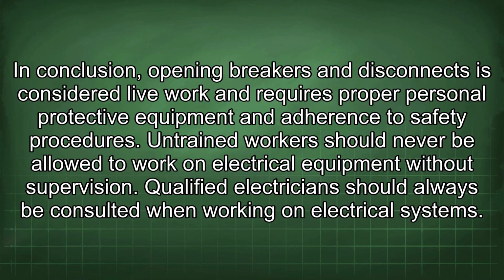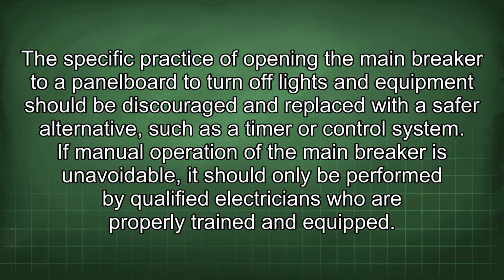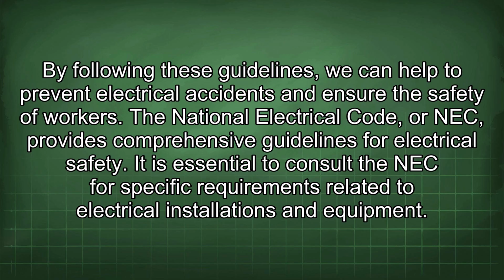Qualified electricians should always be consulted when working on electrical systems. The specific practice of opening the main breaker to a panel board to turn off lights and equipment should be discouraged and replaced with a safer alternative such as a timer or control system. If manual operation of the main breaker is unavoidable, it should only be performed by qualified electricians who are properly trained and equipped. By following these guidelines, we can help to prevent electrical accidents and ensure the safety of workers.